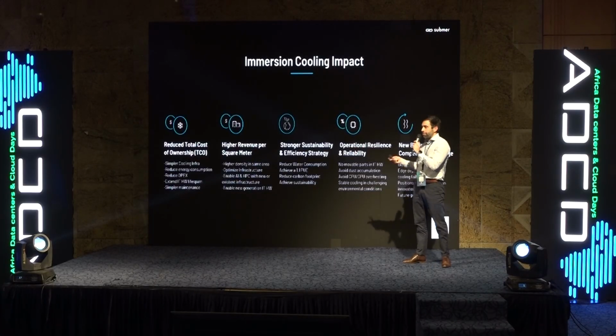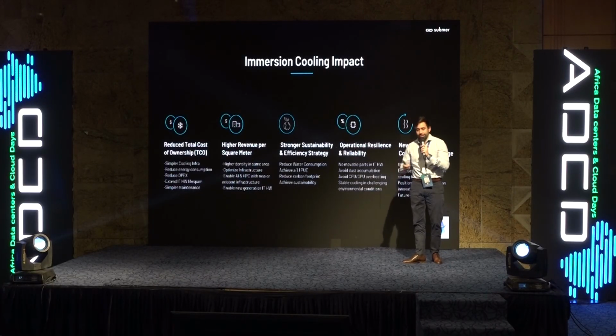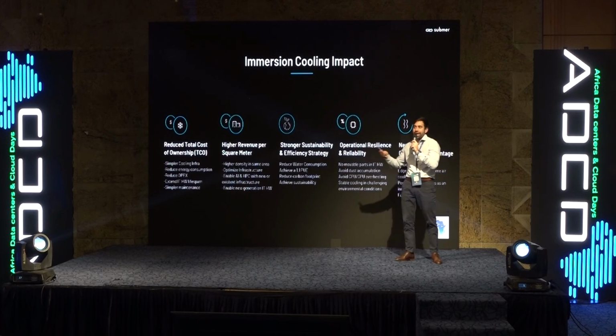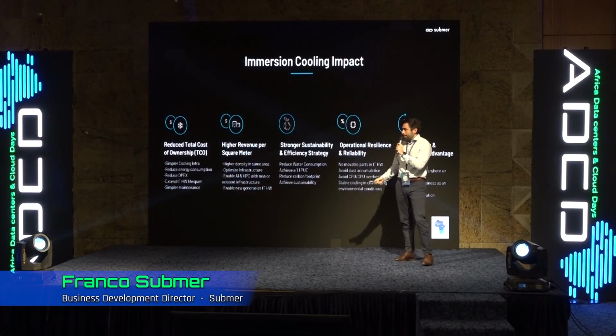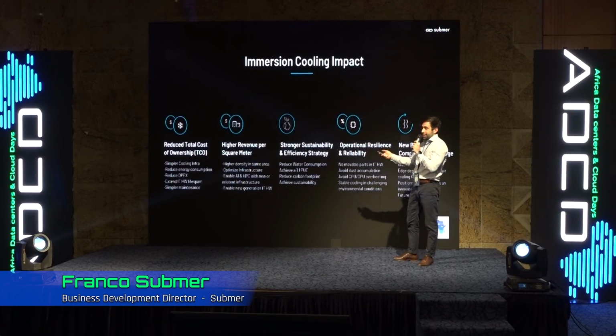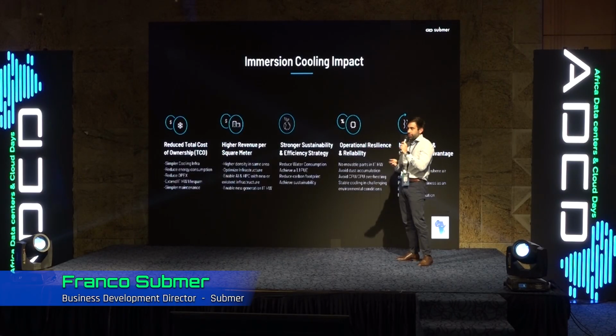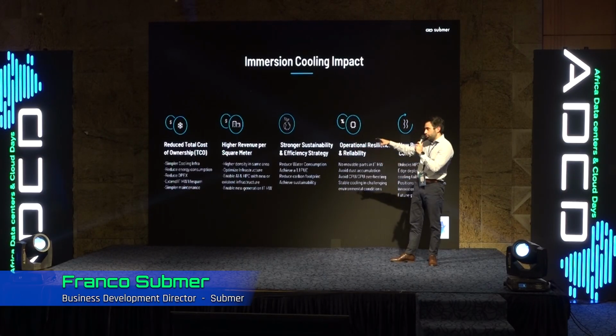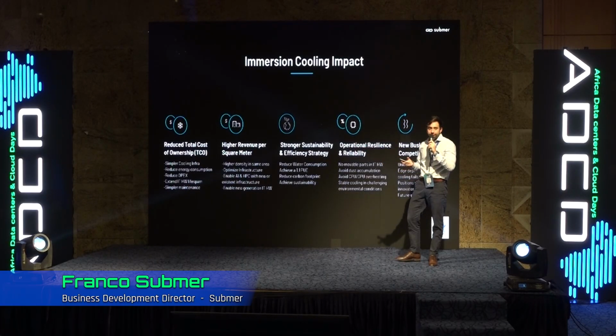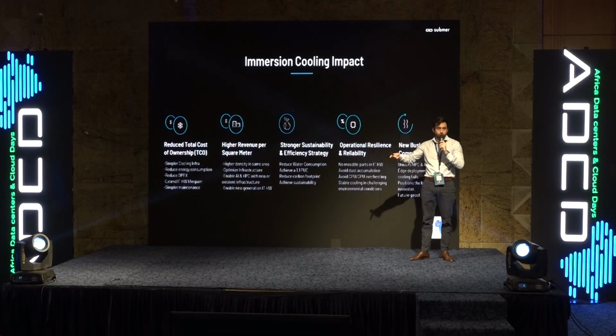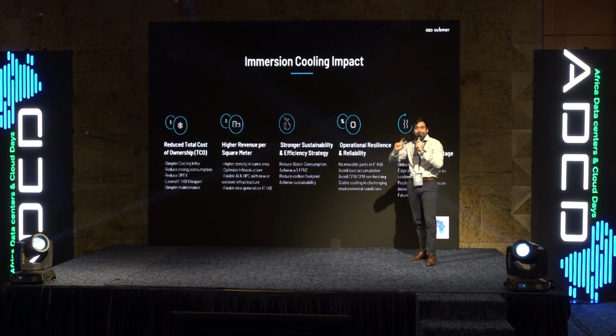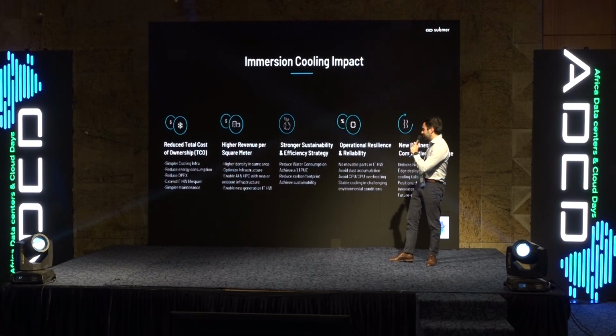Number 2, higher revenue per square meter. Obviously, this will depend on the flexibility you have to obtain more power in your data center and also the capacity to retrofit it. But we can increase the ICT load in your data center if you change from air cooling to immersion cooling. Our solution can have more than 300 kilowatts in a 41U rack. So that's one big advantage you can have using immersion cooling.